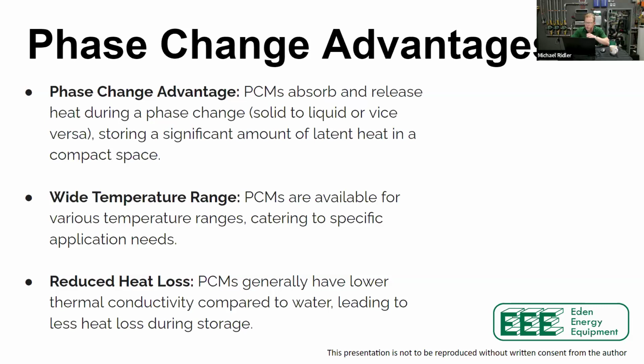The nice part is that once you have that energy stored, the heat loss on these PCM batteries is negligible. We know what manufacturers state for water-based standby losses on a buffer tank, which is traditionally how we'd do thermal storage. But there are other things that come into play: do we have check valves on it, did we pipe it right, did we thermally trap it? These things typically don't happen, including in my own house. I didn't thermally trap my buffer tank because I wanted to see what it would do. By not thermally trapping it, if I charge it to 130 degrees, I come back the next day at 70. With a PCM battery you don't have those same challenges, because the energy is all stored in the PCM battery and only leaves when you're actually flowing through it, so they have significantly reduced heat loss.